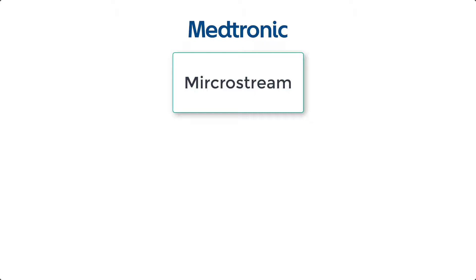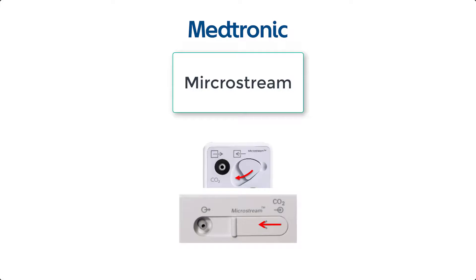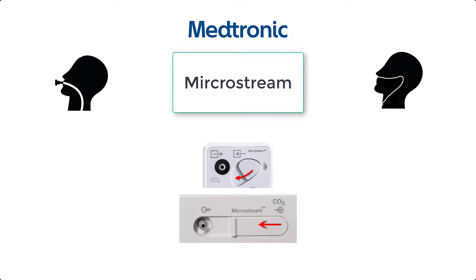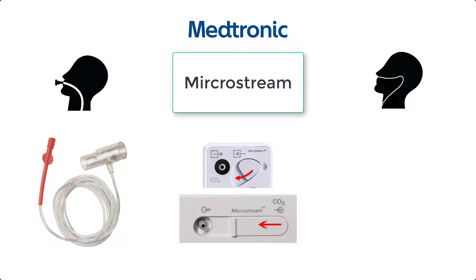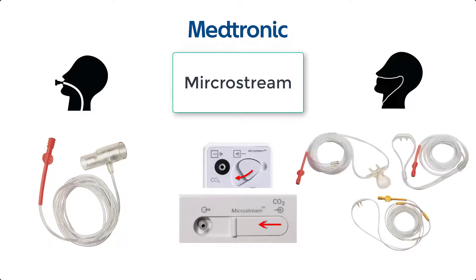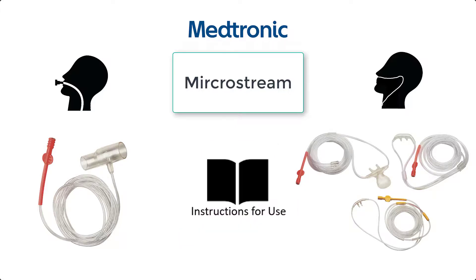To monitor sidestream CO2 with MicroStream from Medtronic, you need the appropriate luer connector on your patient monitor. MicroStream is suited for both intubated and non-intubated patients — use respectively an airway adapter or a MicroStream filter line. The calibration is performed automatically at startup. Read the instructions for use of your Intellivue patient monitor and contact your local Philips representative for further clinical advice.